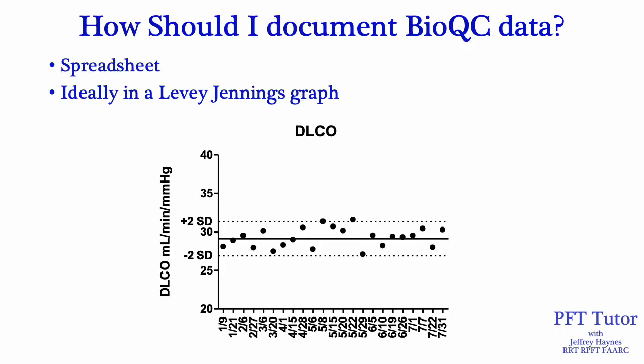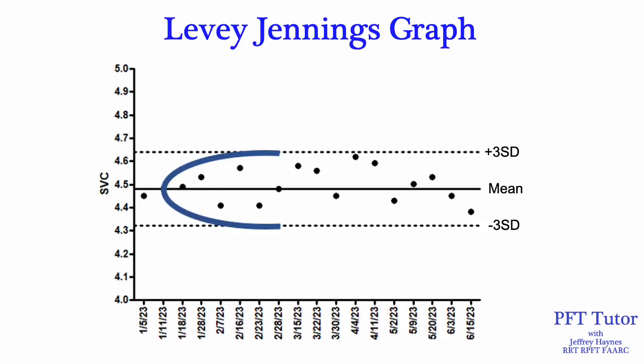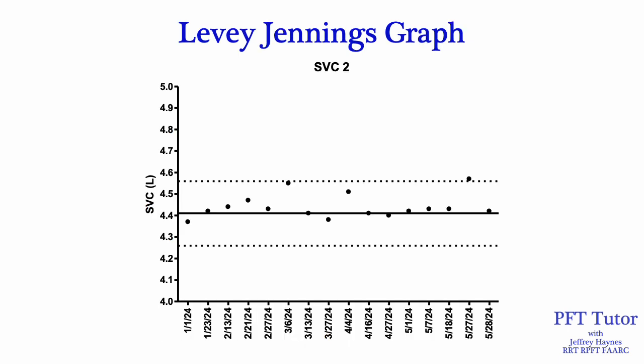How should we document our BioQC data? You could put the data in a spreadsheet with normal ranges, or even a paper worksheet. But ideally, you should plot all this data in a Levey-Jennings graph, just like we'd use for blood gas quality control data. When you look at a Levey-Jennings graph, you're essentially turning that bell curve on its side — the mean value goes to the middle and each end represents the 3 standard deviation range. One benefit of a Levey-Jennings graph is it helps you analyze the data more easily.